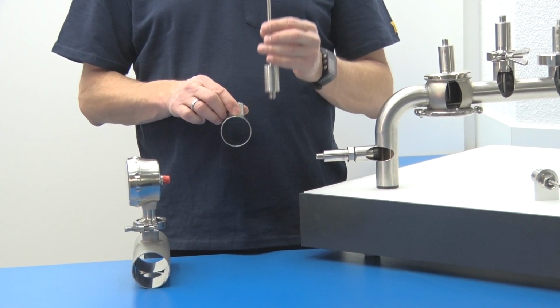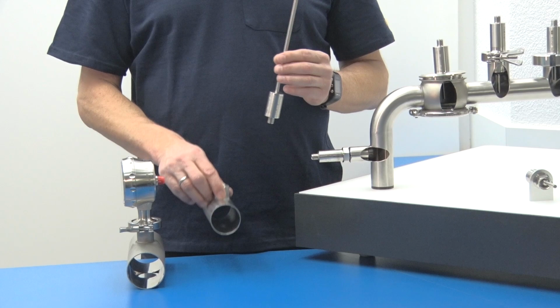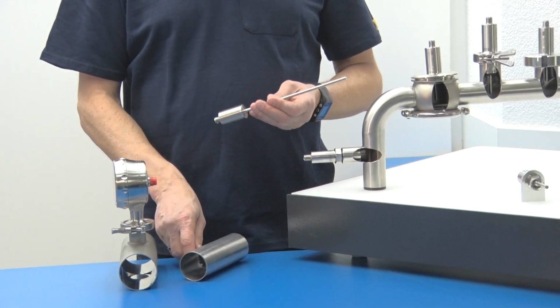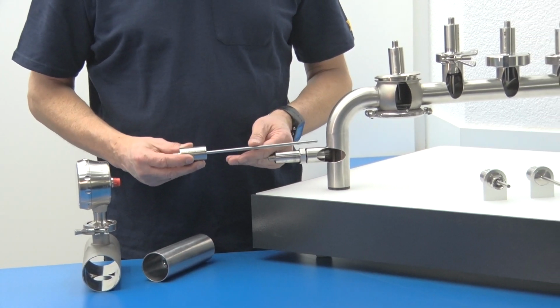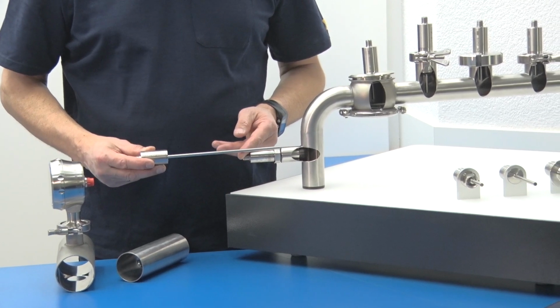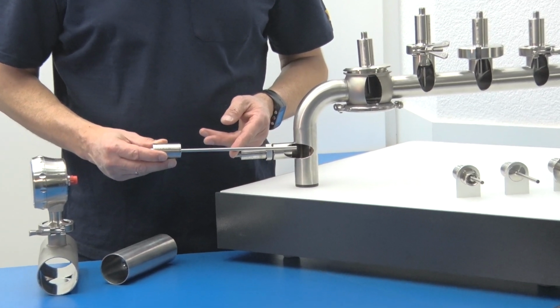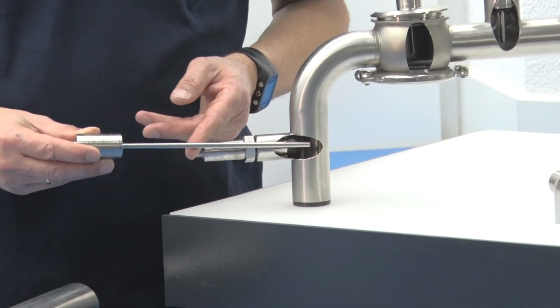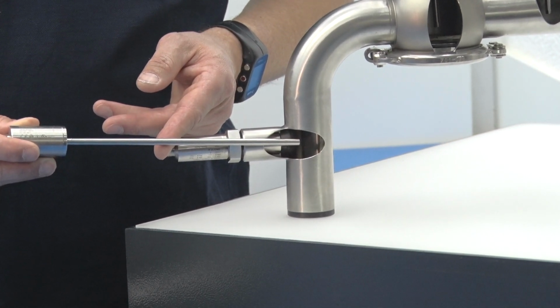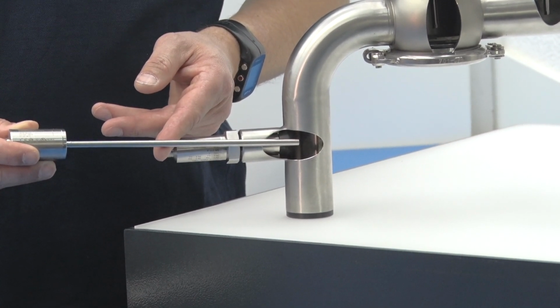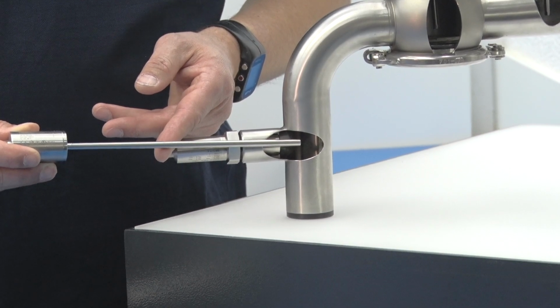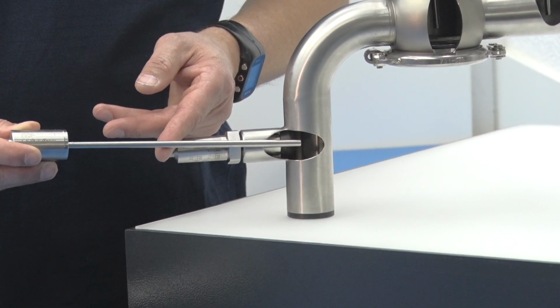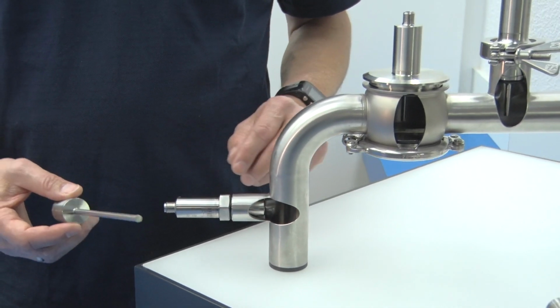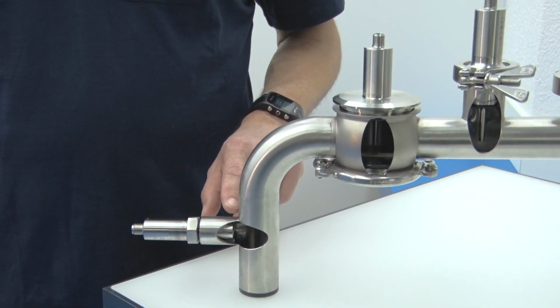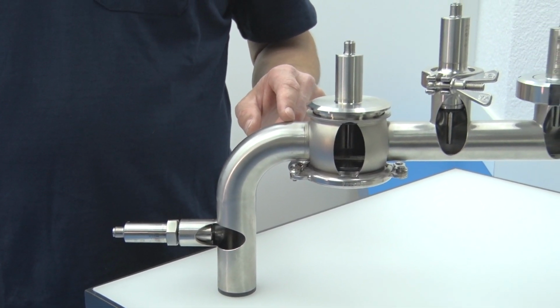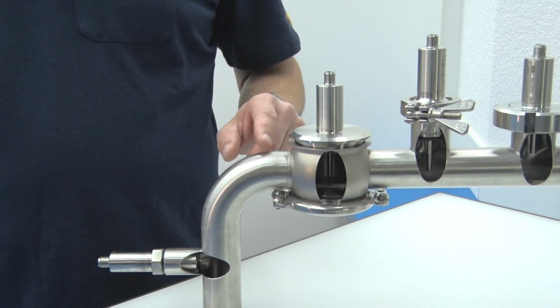For velocity measurement we have a point measurement with the sensor, and therefore the installation position matters. Flow rates are acquired by in-pipe measurements. When we install the sensor here, the position itself, and also which process connection, must be taken into consideration. So, process connection and pipe diameter must be considered for sensor installation.